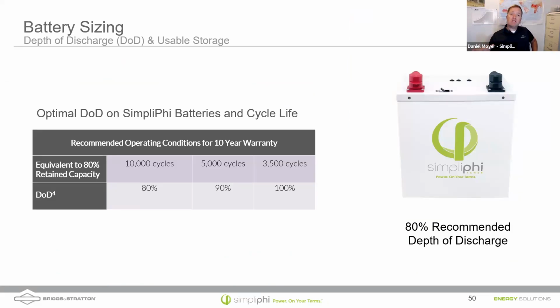When we're talking about sizing, I talked about this a little bit earlier, I'd like to see you size for an 80% depth of discharge. That's going to give you about 10,000 cycles on our batteries. And if you're discharging it daily, right, 10,000 divided by 365 is about 27 years or so. Do I think one of our batteries is going to last 27 years? I hope so. But the point being is the shallower you cycle the battery, the more cycles you're going to get out of it. But it's not like a lead acid battery where we only can go 50%.